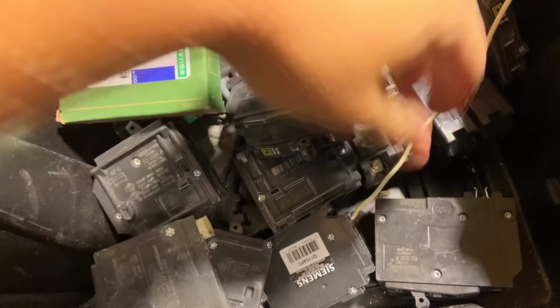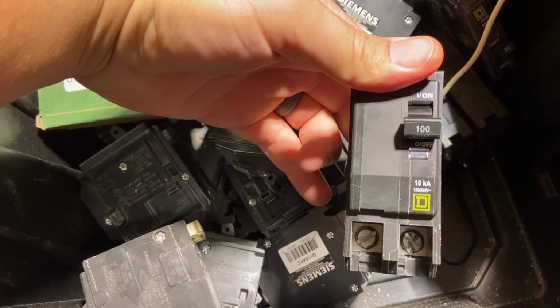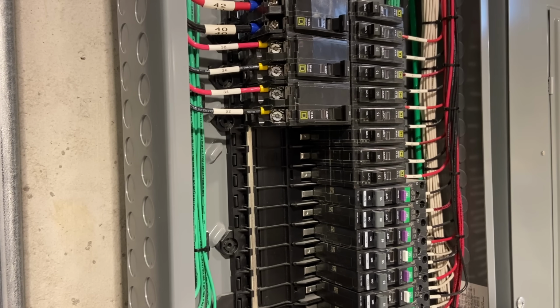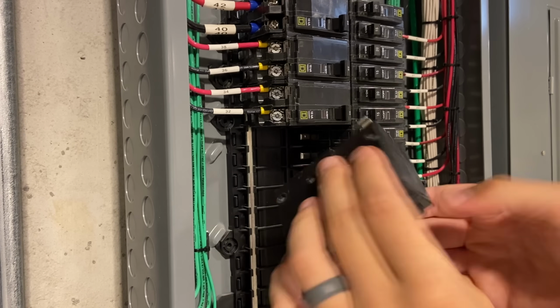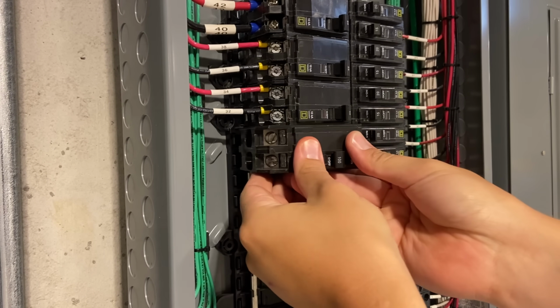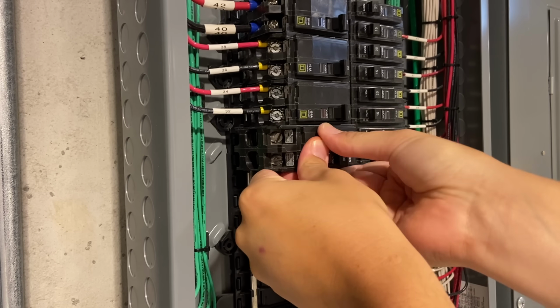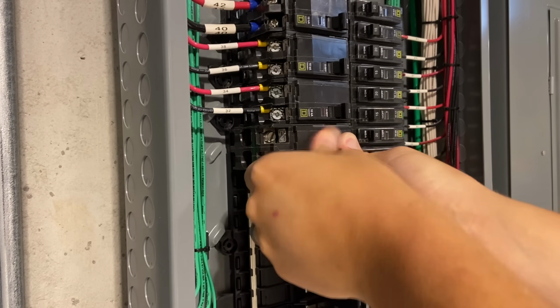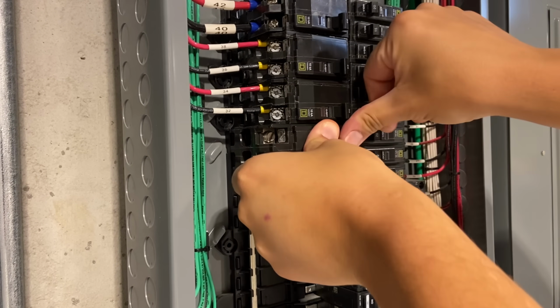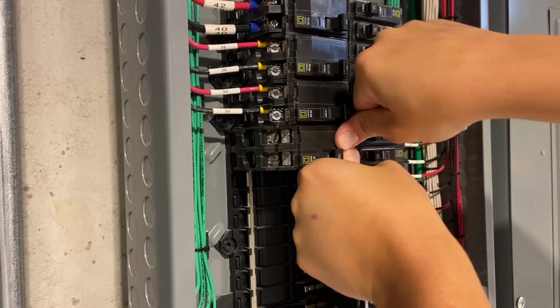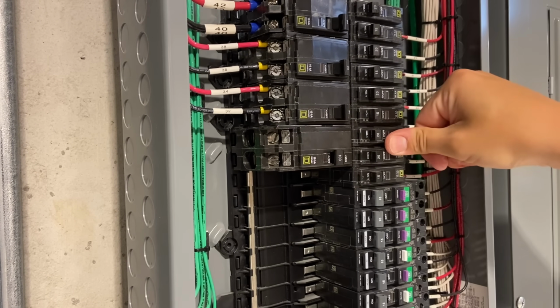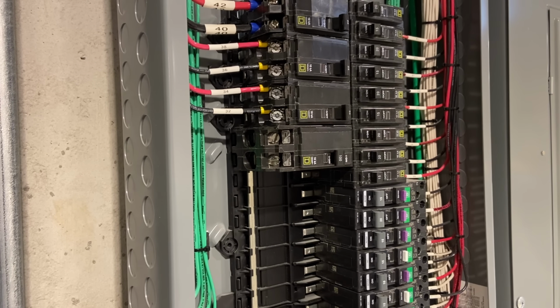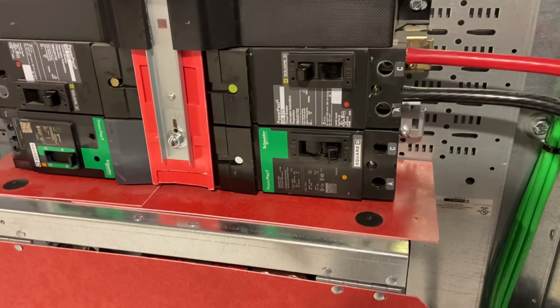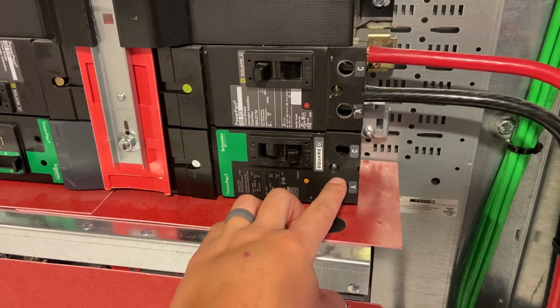Now we just need a circuit breaker for the QO panel, and we'll dig through our pile of junk. There's a 100 amp one with some messed up lugs, but I think we can make it work. This is probably a good time to justify having an I-line panel, because I've never liked putting large amperage breakers in the QO panels. I know you can go up to like 125 or even more depending on the style of breaker, but you're relying a lot on those tabs for a good amount of current. So that's one of the reasons I put that big panel in, for all the larger circuits, I'd rather have something commercial grade.